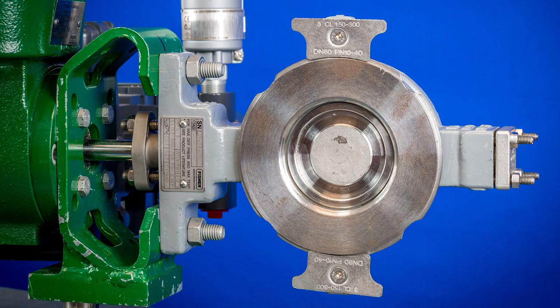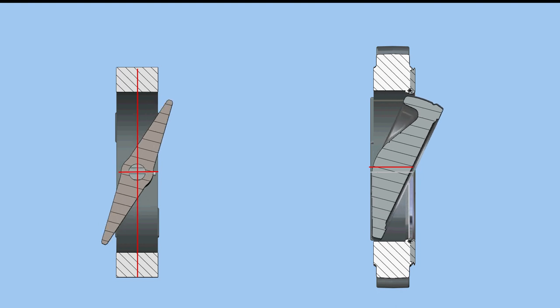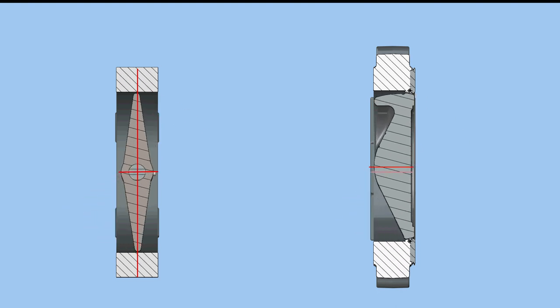These valve designs are high-performance butterfly valves. The drive shaft in this design is offset in relationship to the seal surface and center line of the valve body to minimize contact between the disc and the seal component.